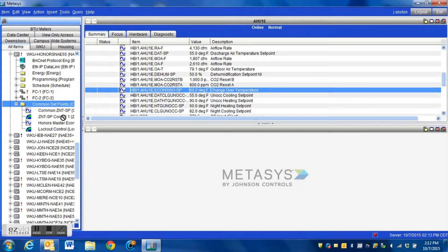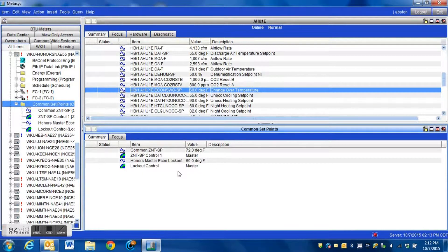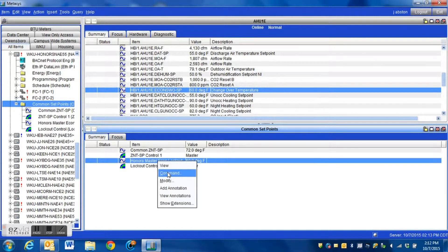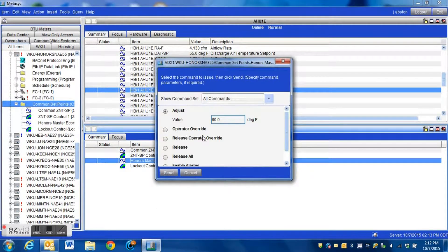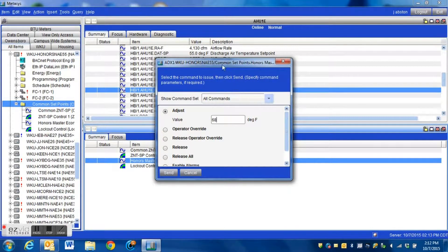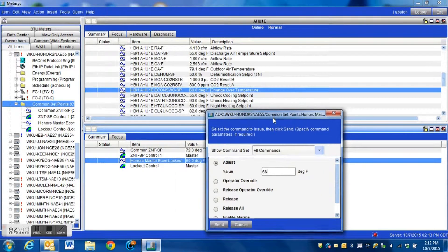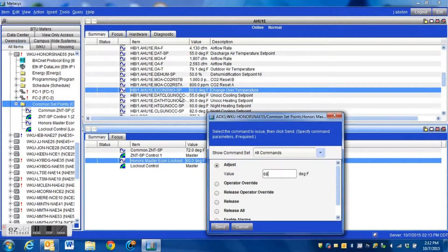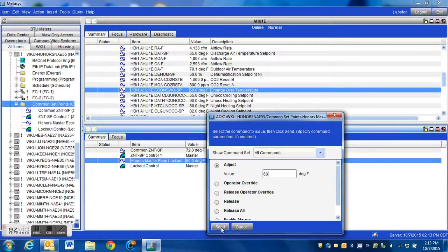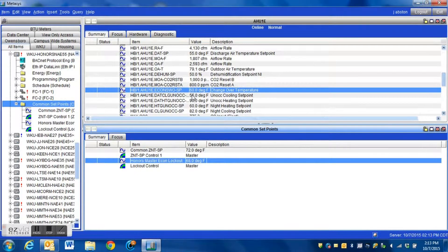We have that set now, you can see the value of this. What we're going to do is I'm going to open up another panel here so we can get a little bit better view of what's going on and I am going to pull over the set point into this window. Now what we're going to do here I'm simply going to command this point, I'm going to adjust it to a different value than what it currently is and if you will watch the set point in the other window you will see it change as well.